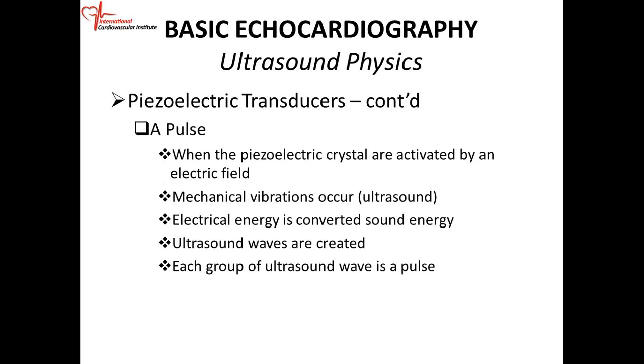Okay? Again, when we talk about a pulse, it is when the piezoelectric crystal is activated by an electrical field. Remember, when you plug your system in, you have your piezoelectric crystals. They're going to vibrate. So the electrical energy is now converted to ultrasound energy or sound energy, and then you're going to have a pulse being created. The pulse may have 2, 3, 4 cycles. The ultrasound waves are created, and each group of ultrasound waves is a pulse.